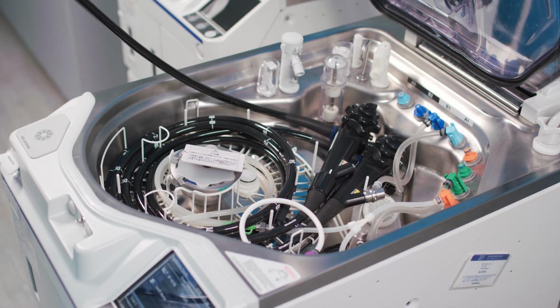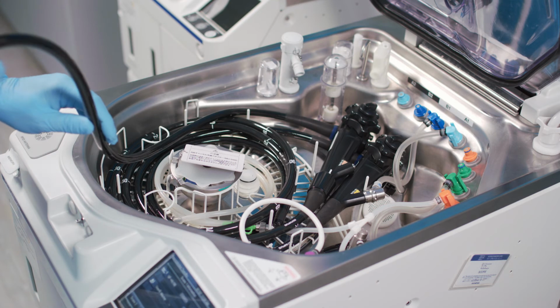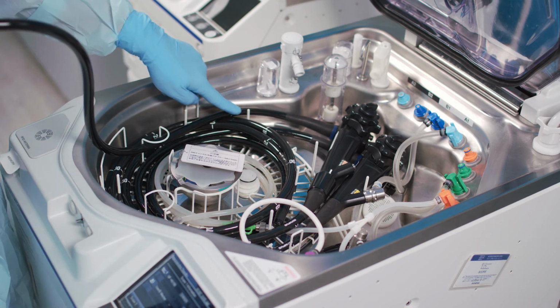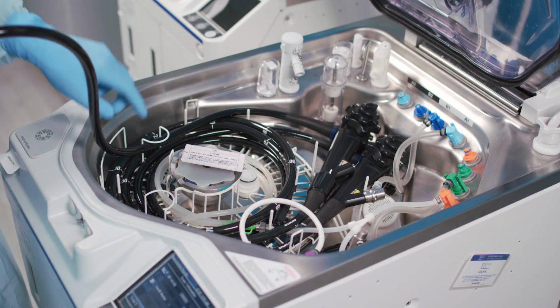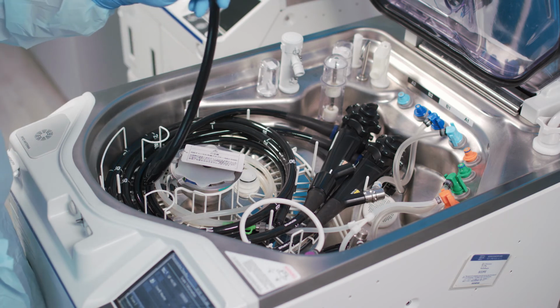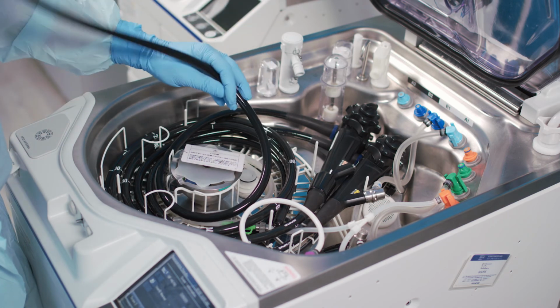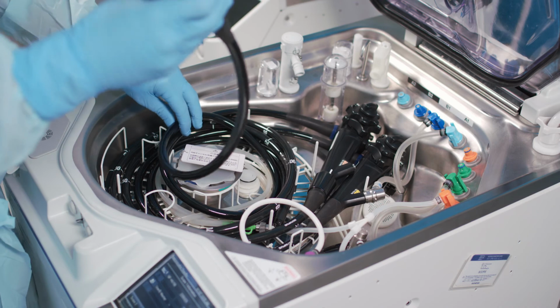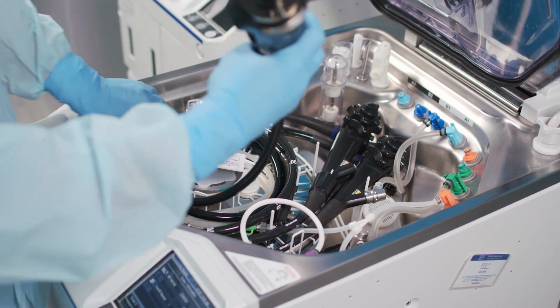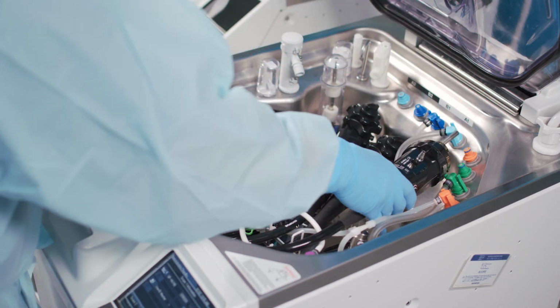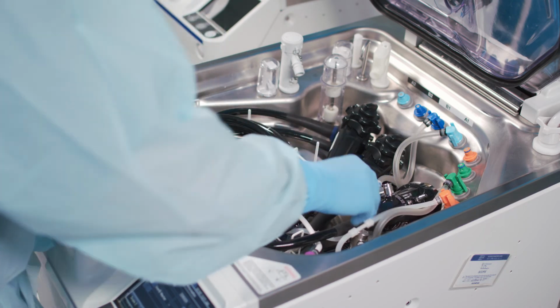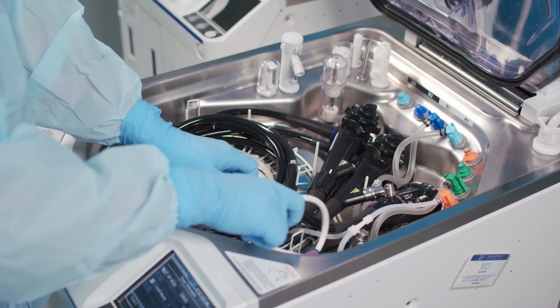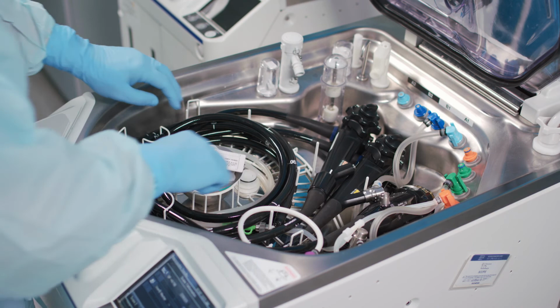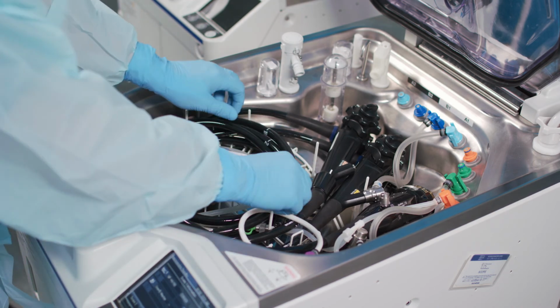Wrap the universal cord counterclockwise around the retaining rack, starting on the left side of the pin and under the hooks of the retaining rack. Place the second endoscope's connector on top of the first endoscope's connector and adjust the position of the insertion tube and universal cord to avoid overlapping as much as possible, as we did earlier in this video with the first endoscope.